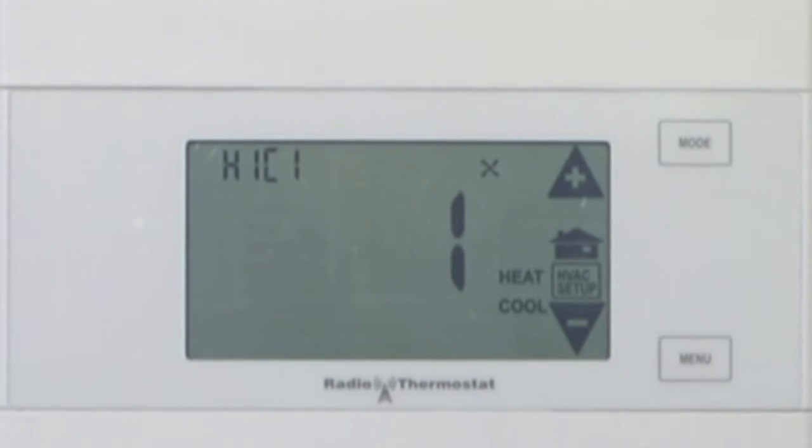That means when you installed the wires, you had a W wire and a Y wire, with no W2 or Y2, meaning you had just one stage of heat and one stage of cool.